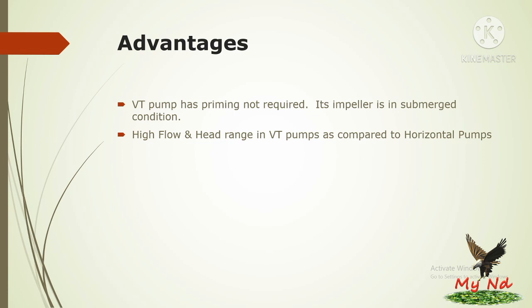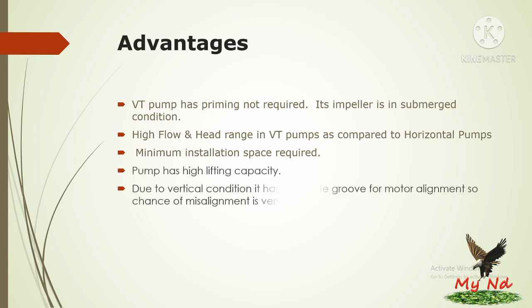It has a high flow and high head range in a VT pump as compared to the horizontal pump. It requires minimum installation space. The pump has a high lifting capacity. Due to the vertical condition, it has a self-guide groove for motor alignment, so there is a minimum chance of misalignment. The motor is always safe in a flood condition.